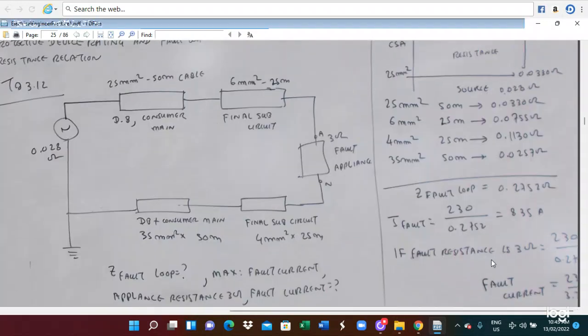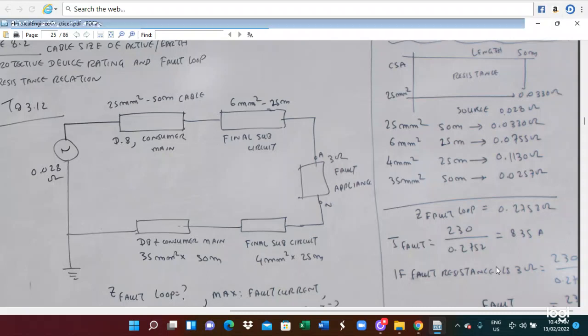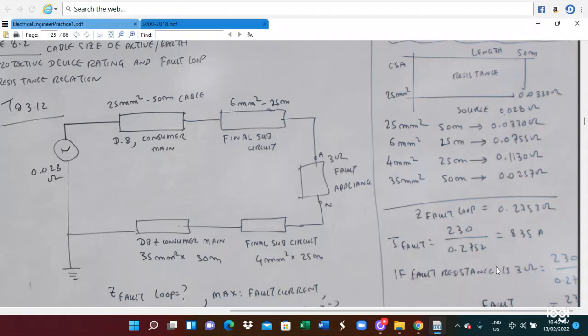In this case, we have to refer to the appropriate table and utilize the manufacturer information. Manufacturer information means the type of conductor, cross-sectional area, length, and the appropriate impedance, so you have to refer to the manufacturer table suitable for your cable. So for this cable, 25 millimeter, 50 meter, you get the value from the manufacturer table. Similarly for 6 millimeter square 25 meter, 4 millimeter square 25 meter, 35 millimeter square 50 meter. Those impedances you add together, and you can calculate the fault loop impedance.